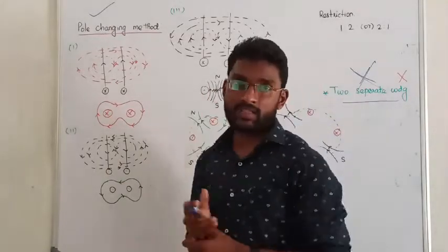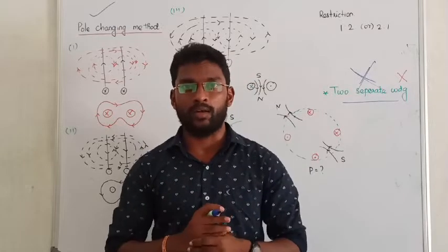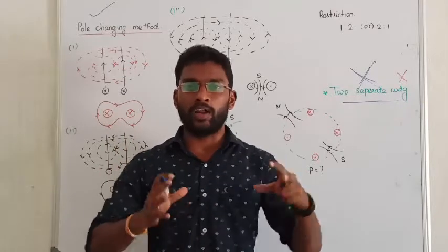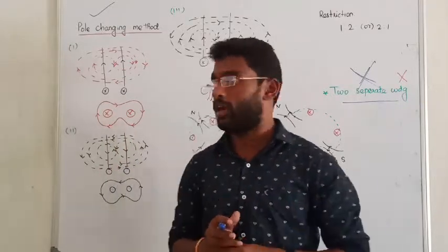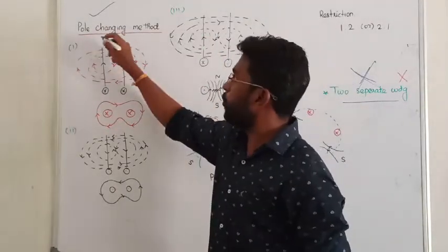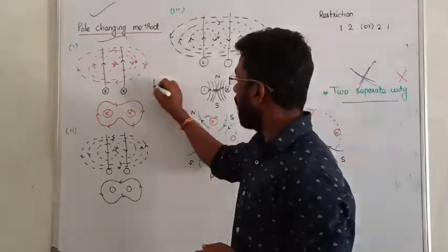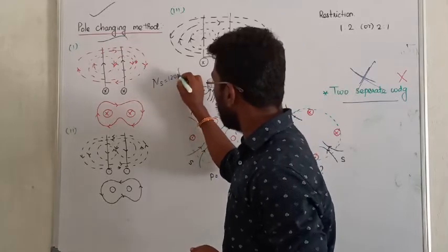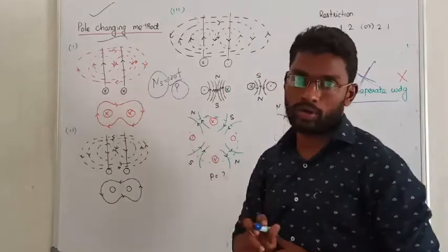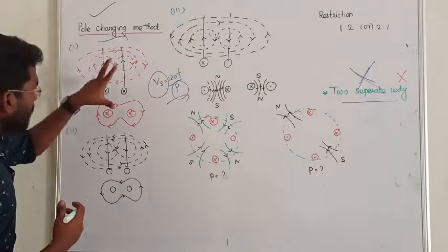What about the squirrel cage? In the squirrel cage, the rotor is just copper bars short-circuited, so you can make any changes to the stator. That is the beauty of the squirrel cage. So let us discuss about the consequent pole changing method. We all know Ns = 120F / P. By changing the number of poles, the speed can be controlled.